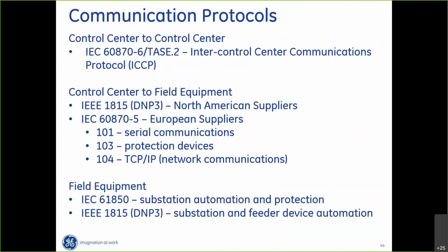From the control center to the field worldwide, there's really two standards. For North America, we use DNP3, now IEEE 1815, or European suppliers will use 870-5, 101 and 104—101 for serial, 104 for network communications. Within the field, again there's really just two: in North America we still use a lot of DNP3, but worldwide the transition is to IEC 61850 as the global standard. So let me finish with a few slides.